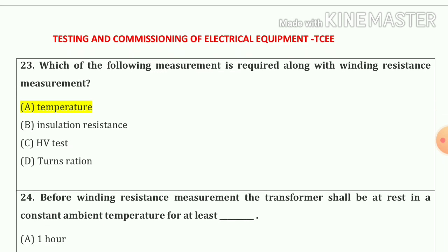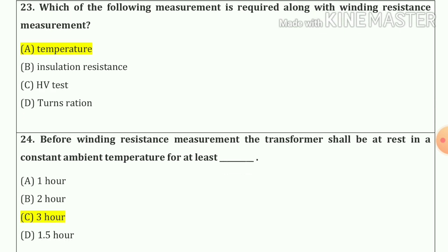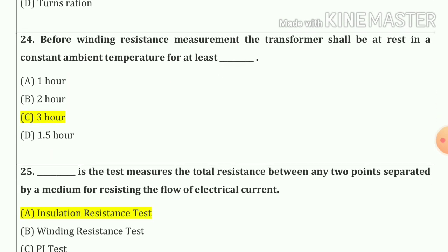Now question number 23. Which of the following measurement is required along with winding resistance measurement? So answer is temperature. Now question number 24. Before winding resistance measurement, the transformer shall be at rest in a constant ambient temperature for at least 3 hours.